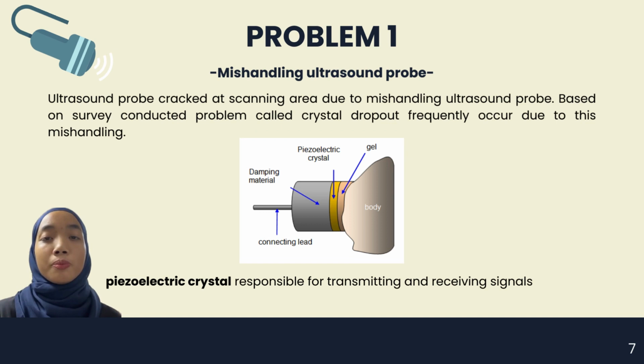Mishandling of the probe might lead to other unwanted issues such as crystal dropout. The probe contains piezoelectric crystals responsible for transmitting and receiving signals. If cracked, a distorted or deformed image will be formed.